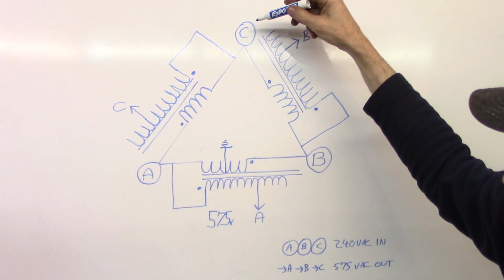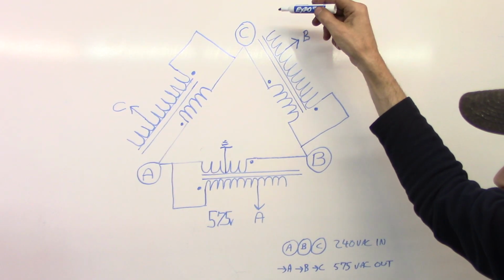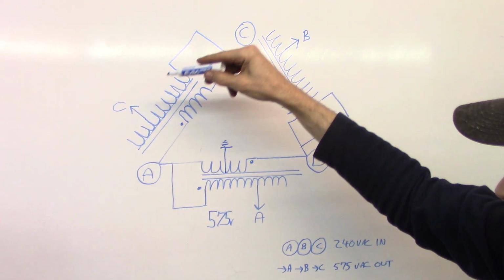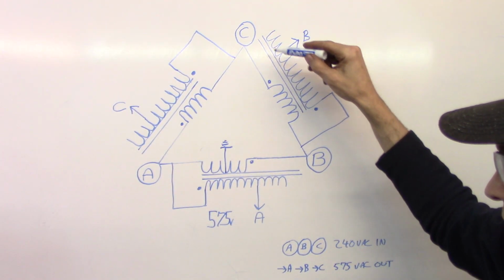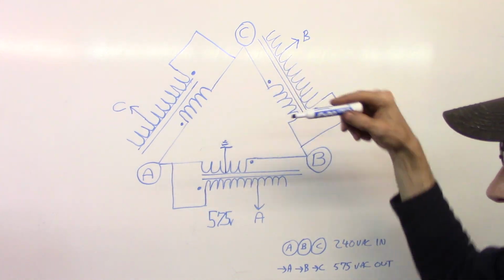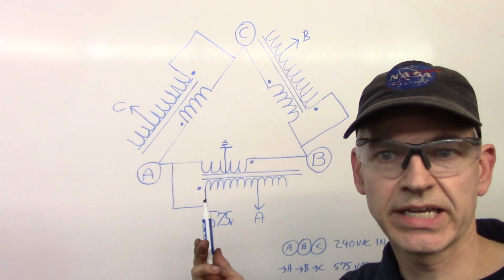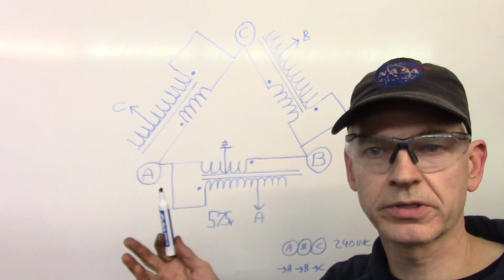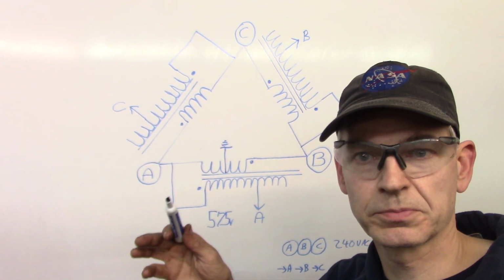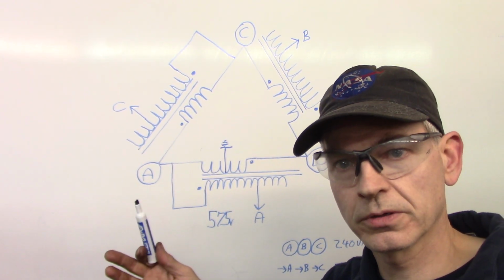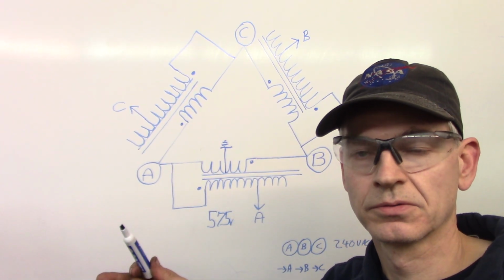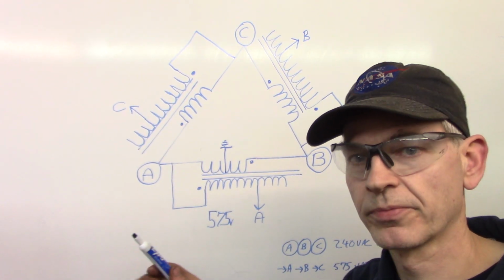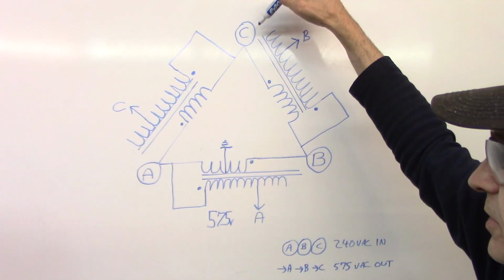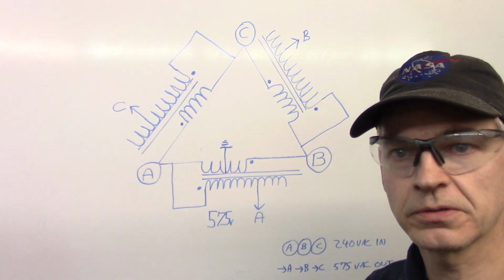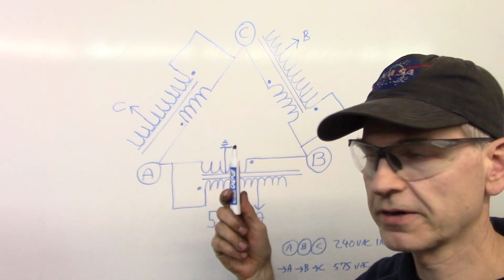With your rotary phase converter, it's a motor, so instead of a transformer drawn in delta here, it's the same thing, except the motor rotates, it spins, it's got a spinning rotor. The transformer does not, obviously, but it's the same 3 coils. If something shorts out in your rotary converter to ground, it trips the breaker.